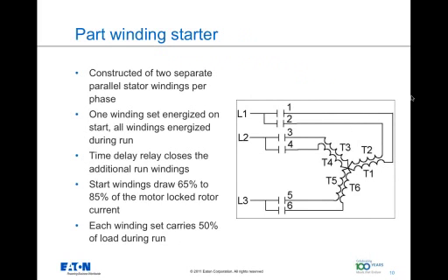The part winding starter configuration has a stator with 2 windings. During the start phase, you energize just 1 winding, and once you hit the top of the ramp, both windings are energized. Starter windings draw anywhere from 65 to 85% of locked rotor current, and each winding set carries 50% of the load during run.